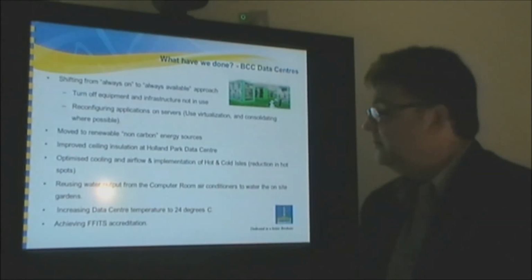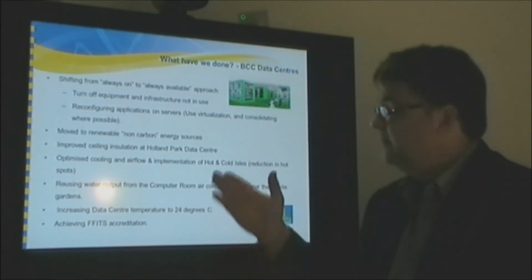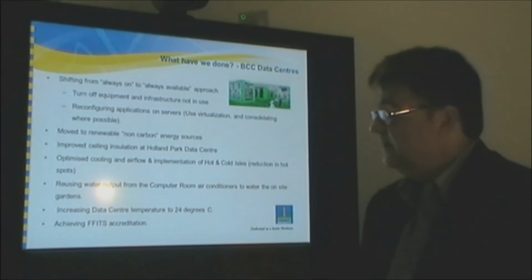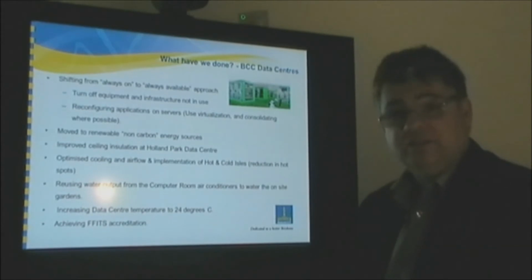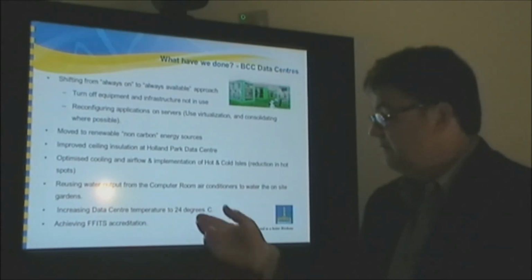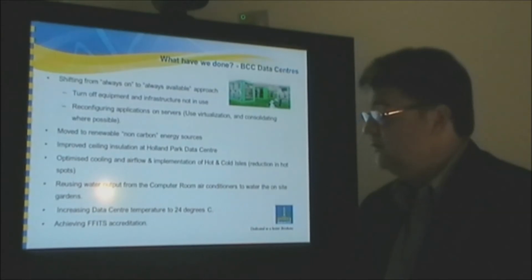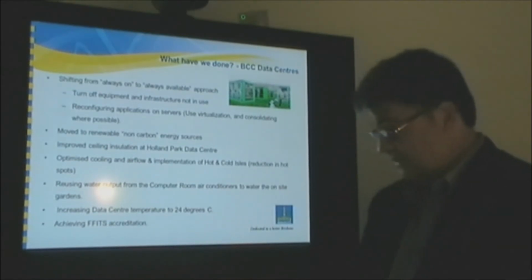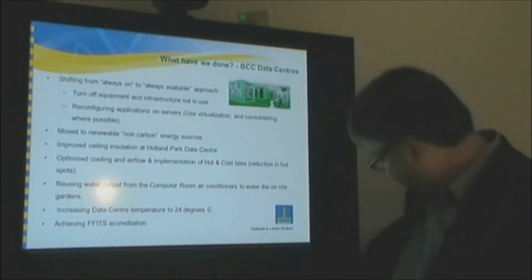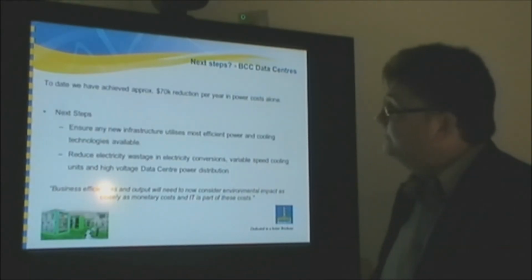We've done a lot of work on our design within our data centres. We obviously have hot and cold aisles, things like that, and we're looking at next steps as we go a bit further down about having those aisles curtained. Even little things like the water output from the computer room air conditioners, using that to water the garden. We've increased the temperature within our data centres, which I believe a lot of organisations are doing now, but we did this some 5 years ago. And more recently, we'll talk about this, achieving the FITS accreditation around our data centre operation. So that's what we've done.